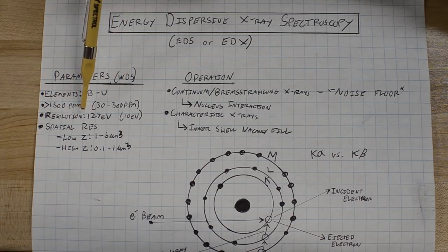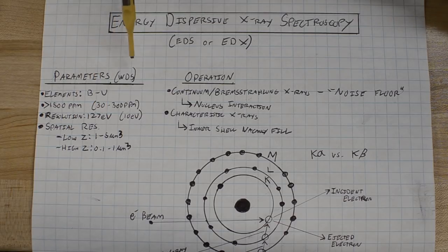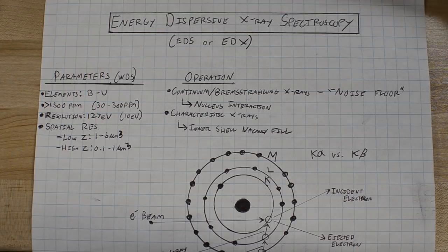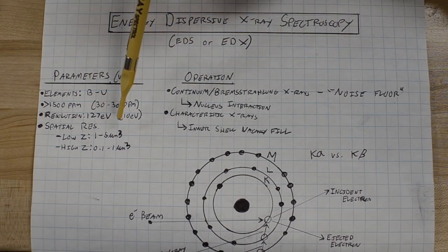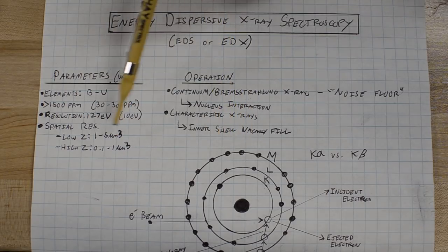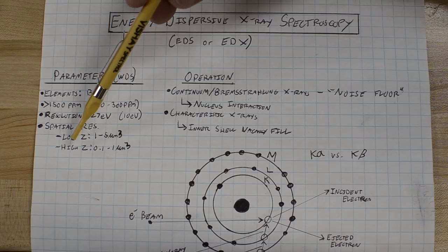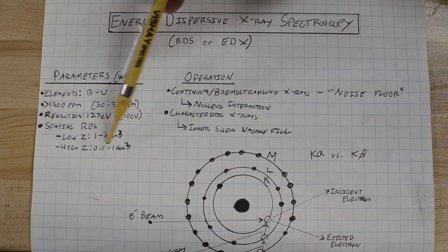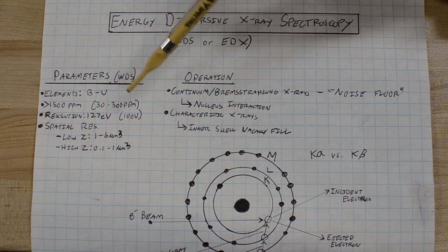The resolution of the system I have here because it's a silicon drift detector and not an old silicon lithium detector is 127 electron volts and that's quite good. The spatial resolution is the amount of the sample that's actually excited when the incident beam hits the sample. For low atomic number samples that's between 1 to 5 cubic microns and for high atomic number samples that can be considerably smaller.